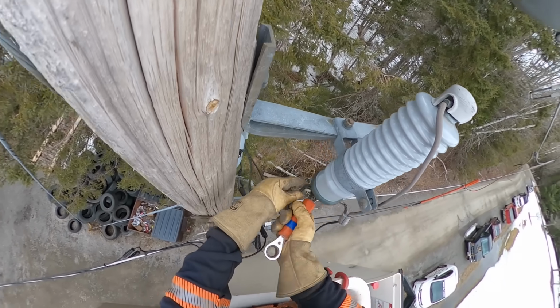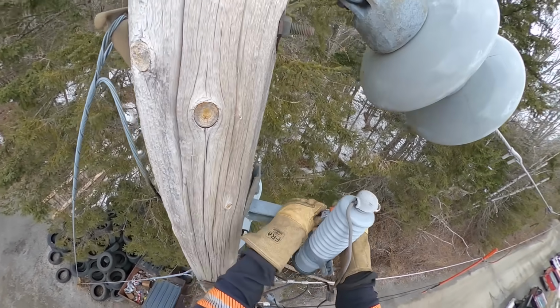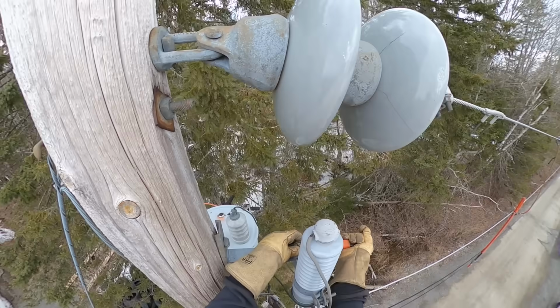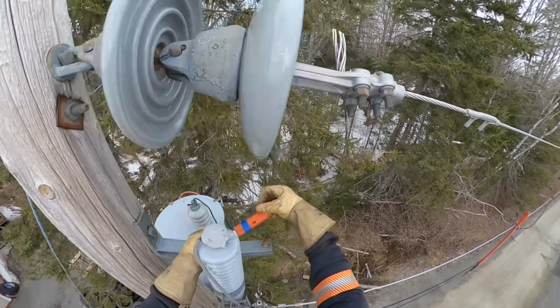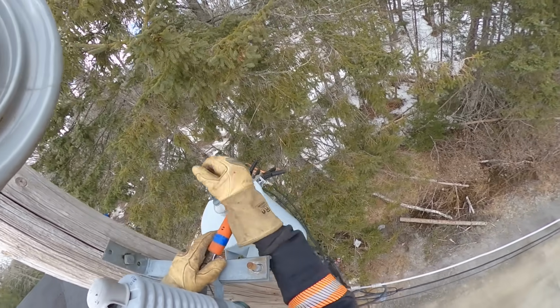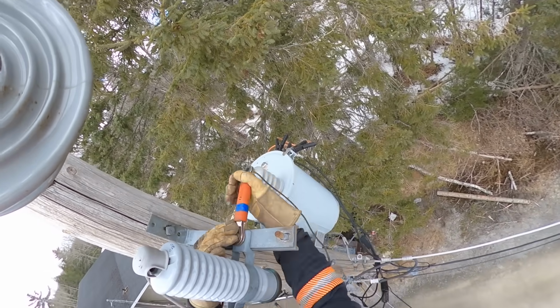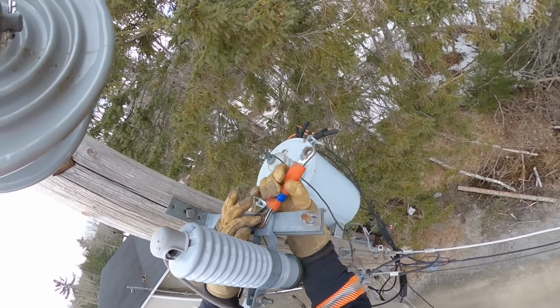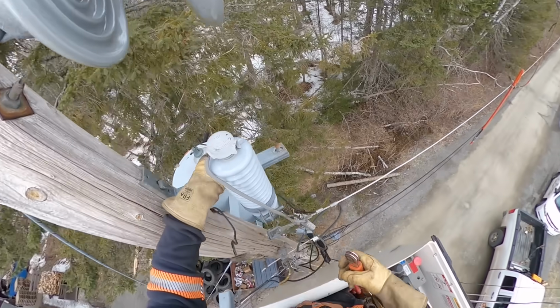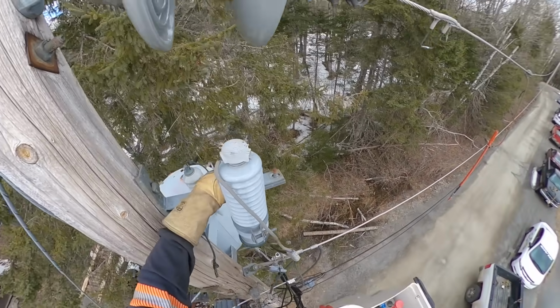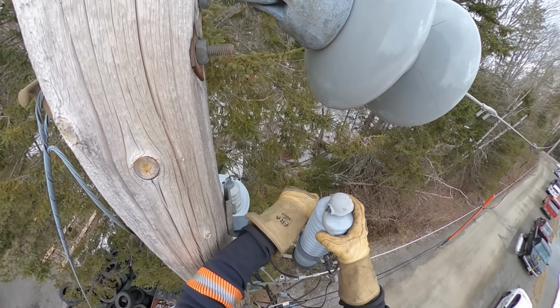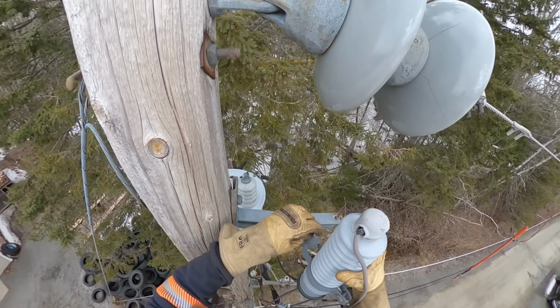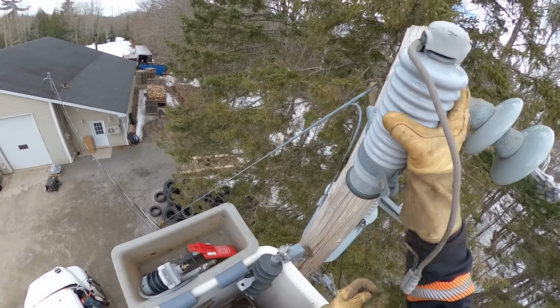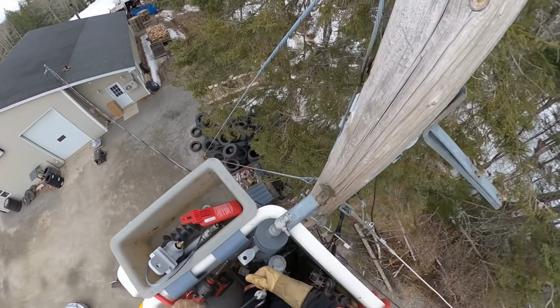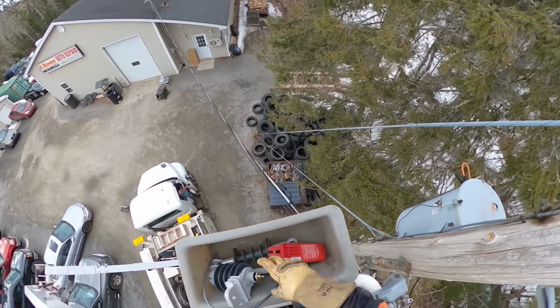Those lightning arrestors come mounted on the transformers nowadays, so that way if they do happen to blow or take a hit, it's not going to take out the whole sideline. It'll blow the fuse particular to that transformer instead. It's a much better setup. You can see the cracks in the porcelain in the back there. They're pretty obvious in this case. Like I said, we could see them from the ground. A lot of times you can't see them at all.